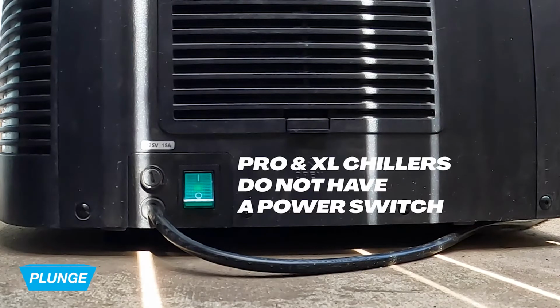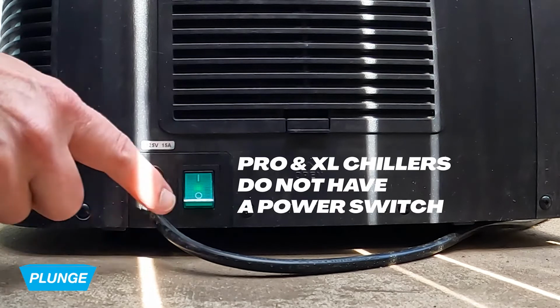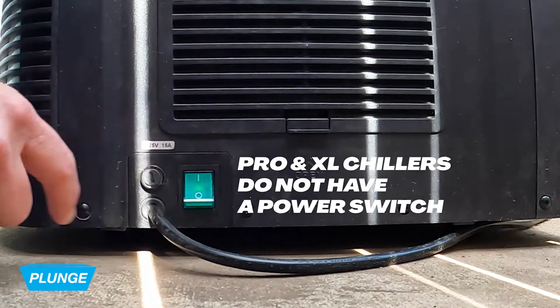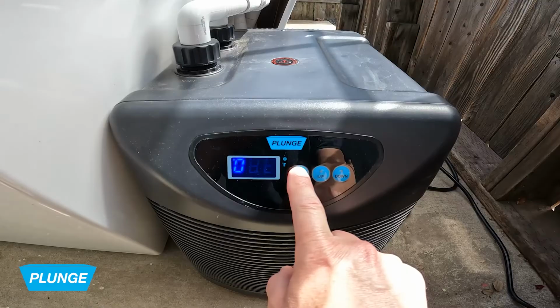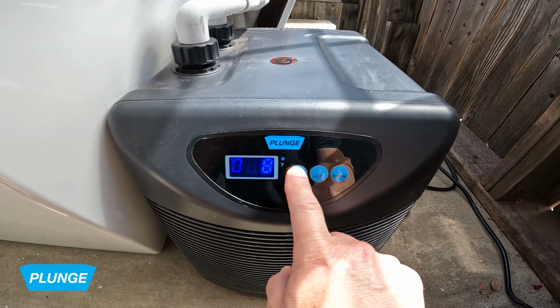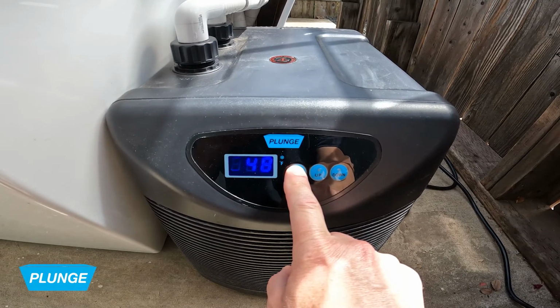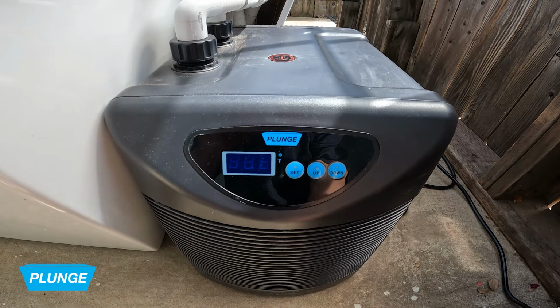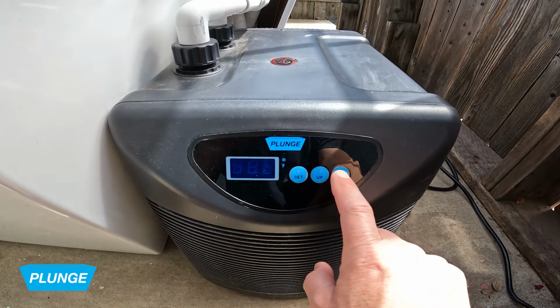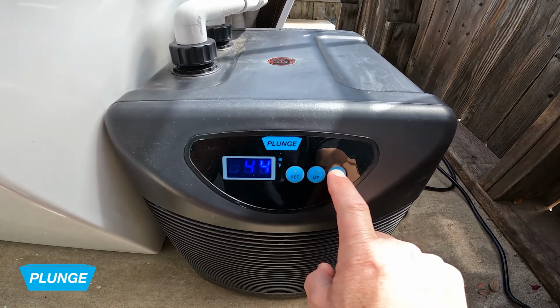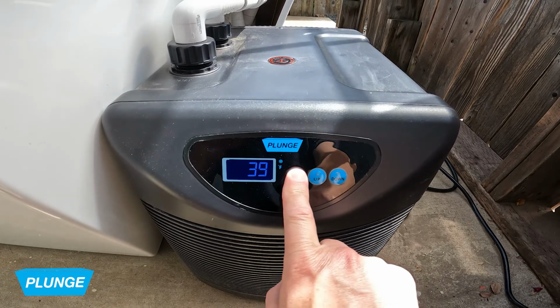Now we're going to set the temperature on our chiller. Important to note, for all of our standard units, we want to make sure that the green switch is on the side of the chiller. The chiller should be set to 39 degrees. Push and hold set until it beeps, and then lower the temperature down to 39. Once set to 39, do not adjust this temperature.